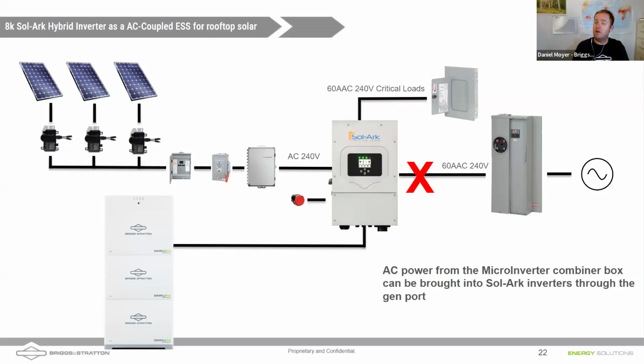We can technically also land that solar on the critical loads panel, right? AC couple on the loads side of things, say if we did want to use a generator. The problem is that we're going to lose that telemetry. We're not going to know exactly how much solar we're producing, because some of that might be consumed by some of the loads in that panel. But either way, that's the architecture we used on the job I was doing yesterday. We brought that AC coupled solar onto the load center just because it worked a little easier on the house.